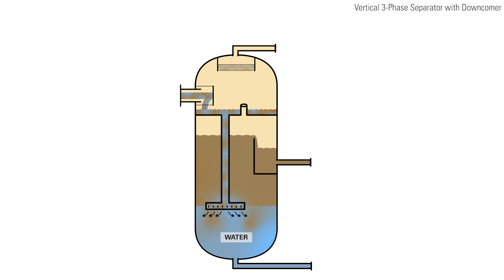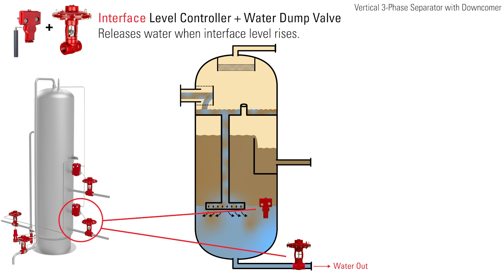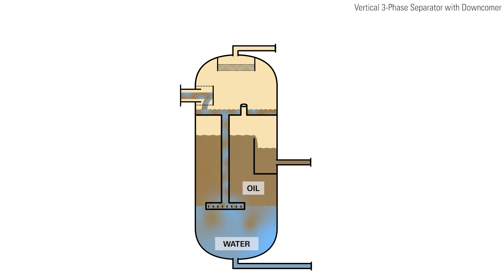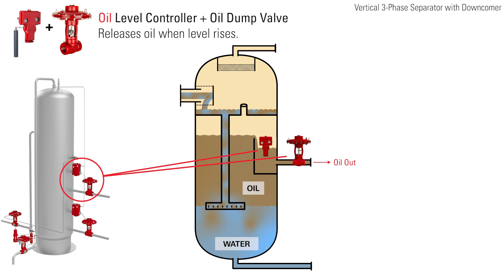Water, being heavier than oil, will separate and settle to the bottom of the vessel. The interface level controller will open the water dump valve when the interface level rises. The lighter oil will separate out and rest on top of the water, with the oil level in the vessel determined by the weir height. Oil flows over the weir and into the oil bucket, and this oil level in the bucket is controlled by a level controller, which opens the oil dump valve when the level increases.